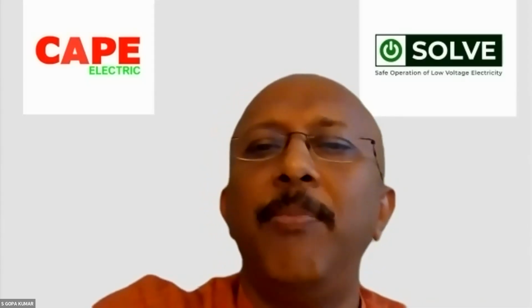What is the allowed voltage between neutral and earth? Is it less than 1 volt? There is nothing like that. There is no allowed voltage or disallowed voltage. Voltage between neutral and earth can go up to 230 volt in an unearthed system. Okay, John Varghese is asking, what is the reason for computer professionals to keep neutral voltage close to 0? I really don't know. That is not at all required. If you are talking about the neutral to earth voltage between the 3-pin plug, because your computer has a 3-pin plug, the voltage between the earth pin and the neutral pin is absolutely not required to be near zero. It can go even up to 230 volt.